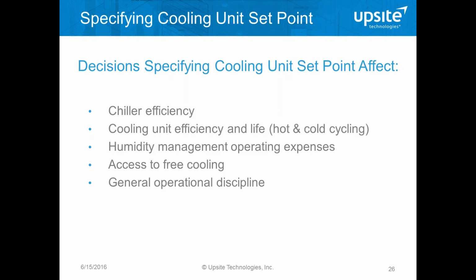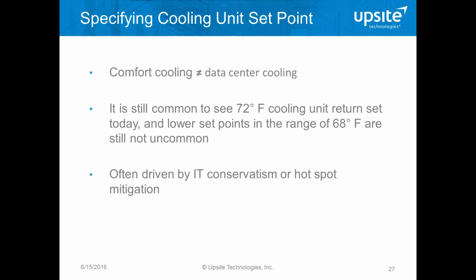We're also looking at humidity management expenses, access to free cooling, and general operational discipline. If we're responding to problems in the data center with hotspots or cooling issues by increasing airflow and reducing set point, we're masking those kinds of problems that the discipline of good airflow management, which Lars will be talking about at the end of this, would allow us to have access to all the other benefits we've talked about up to this point.